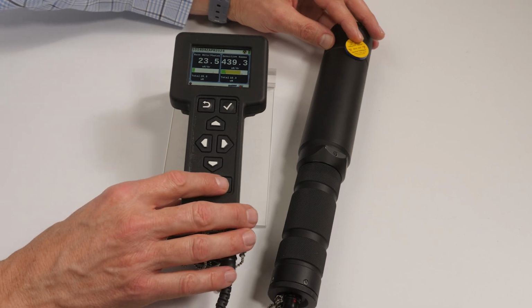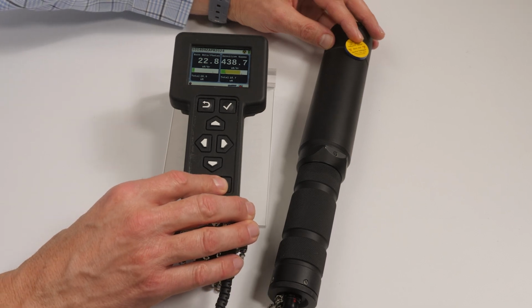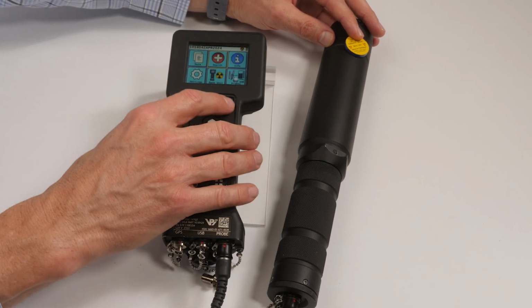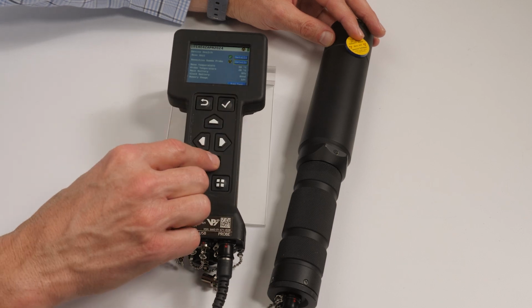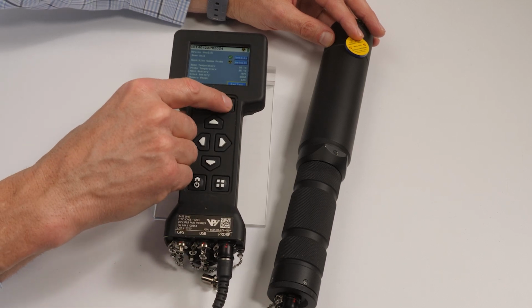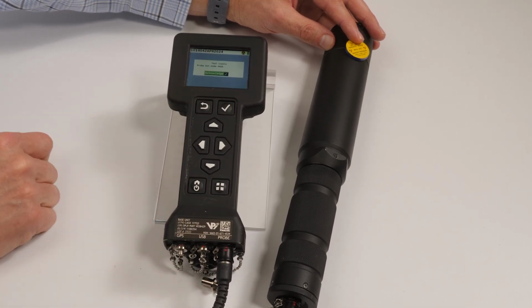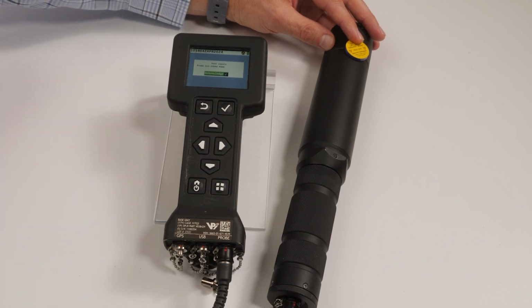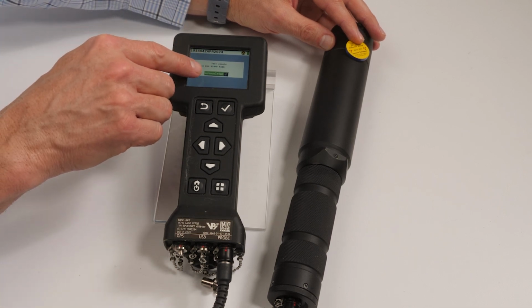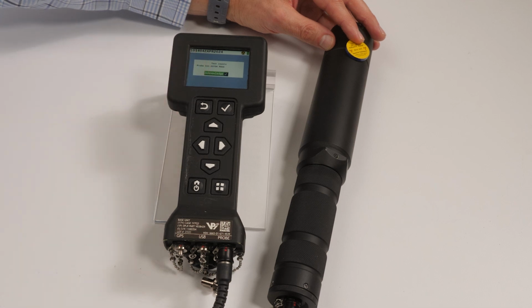Next, perform a rad test. Press the menu key, press the health icon, and press Enter. Highlight the rad test button and press Enter. Leave the sensitive gamma probe in direct contact with the check source for 1 minute. Verify that the probe CNT displays at least 1 count or higher and displays Pass. After the 1 minute, press the Enter key to acknowledge the rad test results.